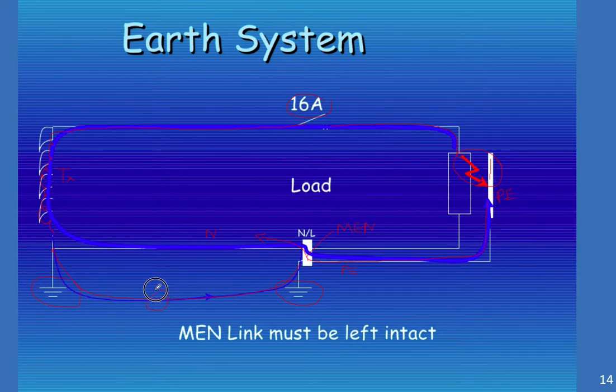It can go back to the transformer via the MEN link and the neutral. This is the neutral, this is my protective earth. And the two are connected here with the MEN. But I can also, you'll see a smaller line here, there can be current flowing back to this point via what we call the body of earth. The impedance of earth is moderately high, well above zero ohms.